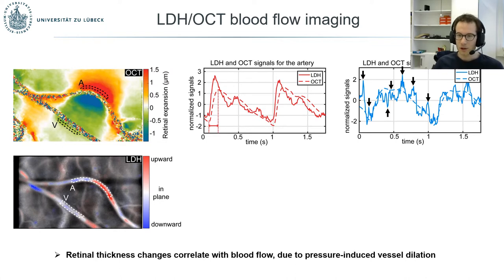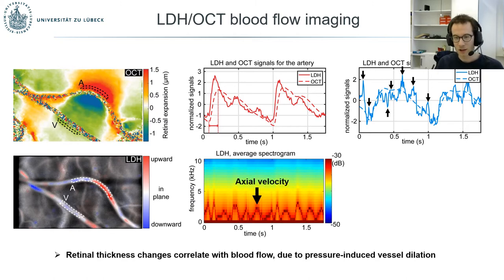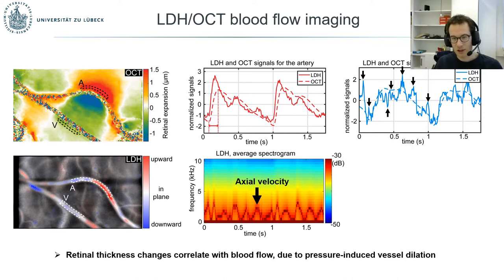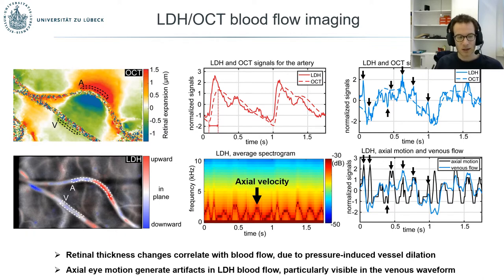However, we were not totally satisfied, as some deviations between LDH and OCT signals remained, especially in the venous signal. We wondered whether this was due to fast blood flow fluctuations undetectable with OCT, or LDH artifacts. It turned out to be the latter: the deviations were correlated with the axial velocity of the eye, which can be very precisely monitored with LDH. The axial motion of the eye is not totally suppressed by the eigendecomposition in LDH, and generates artifacts particularly visible in the venous waveform because its amplitude of variations is lower than in the arterial signal.